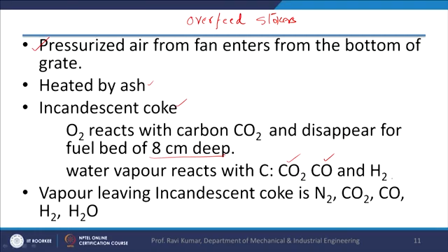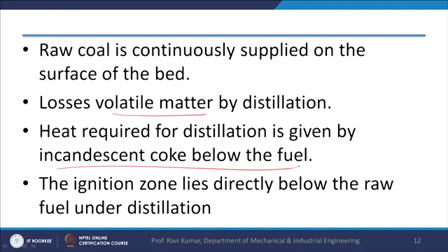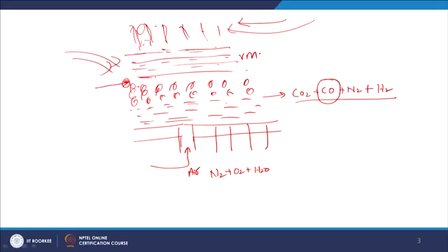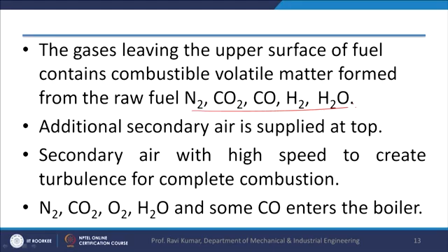The raw coal, as I mentioned earlier, is continuously supplied on the surface of the bed. Distillation of the volatile matter takes place in the green coal bed when the hot air enters from the bottom. The heat required for distillation is given by the incandescent coke below the fuel. The ignition zone lies directly below the raw fuel under distillation, somewhere here. Here the ignition of the fuel takes place. The gases leaving the upper surface of the fuel contain combustible volatile matter formed from the raw fuel. Secondary air is supplied from the top, and this is how combustion takes place in the overfeed type of system. Now, we will go for the underfeed type of system.